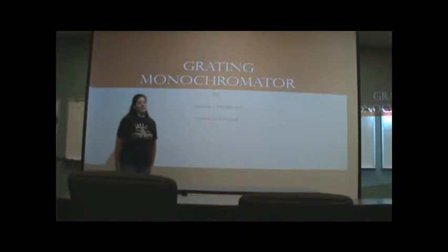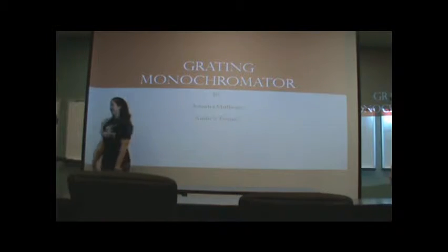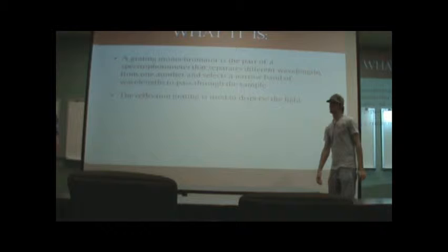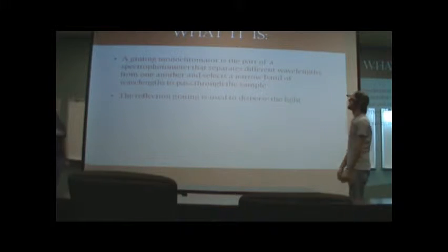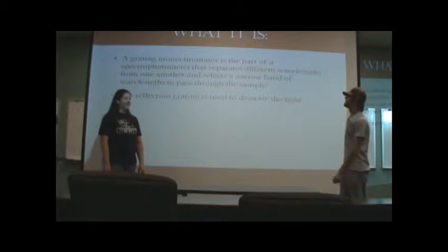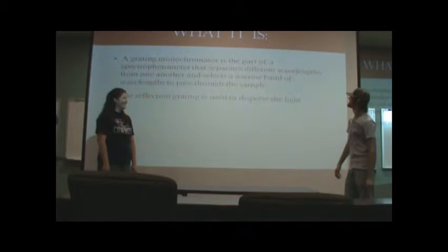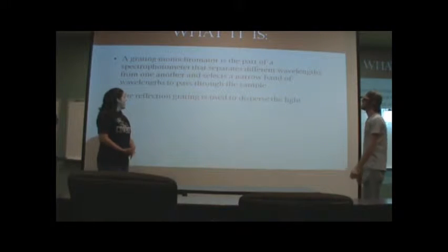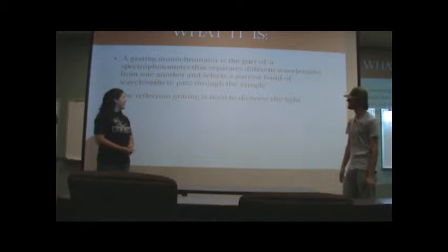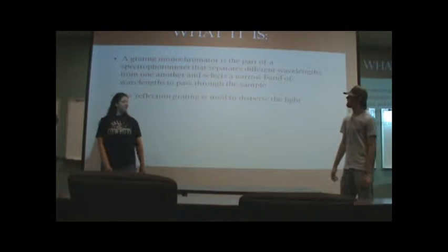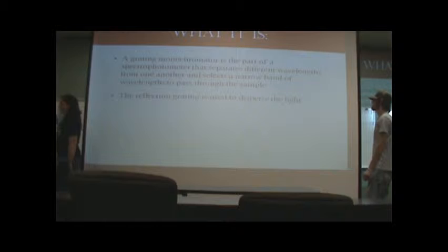I'm Jennifer Mulligan, and my partner is Andrew Bogart, and we are doing our presentation on grating monochromators. I'm going to talk to you today a little bit about what it is. A grating monochrometer is a part of a spectrophotometer that separates different wavelengths from one another and selects a narrow band of wavelengths to pass through the sample. The reflection grating is used to disperse the light.